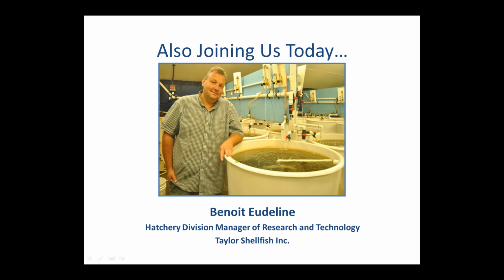And finally, and I know this has always been a big challenge for us, calibration. Todd mentioned the 1-point calibration, and so far we have not been doing that. Despite their low drift over time, as I mentioned, we calibrate the probes once a month, and initially we were told to use 2 saltwater buffers to calibrate this probe, one TRIS buffer and one AMP buffer. But we quickly realized that since we were using the UDA2182, this was not possible, because you get an error message telling you that the span between the 2 buffers is too small, and so it cannot calibrate. So then we had to go to a more traditional calibration technique using regular freshwater NIST buffer.